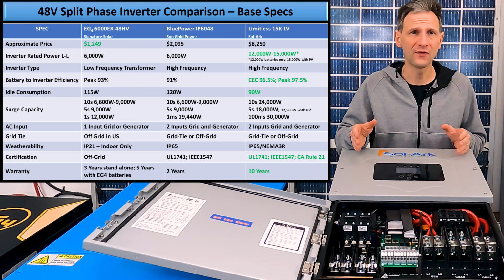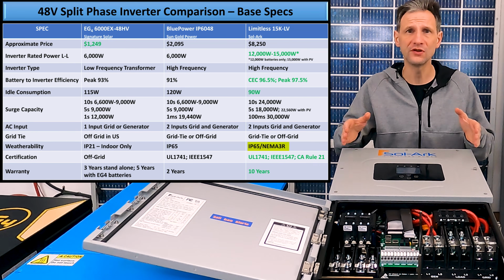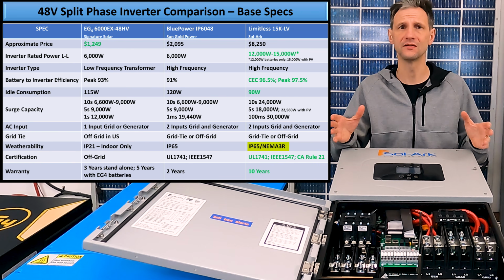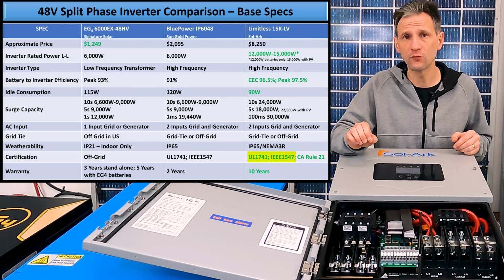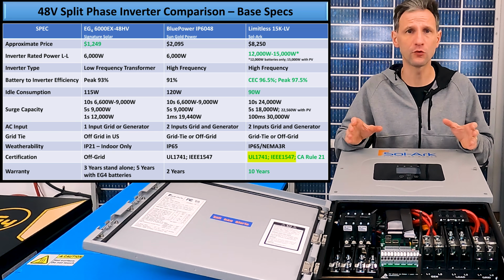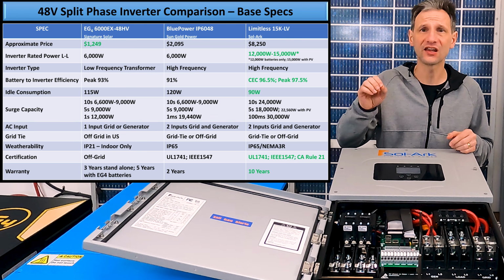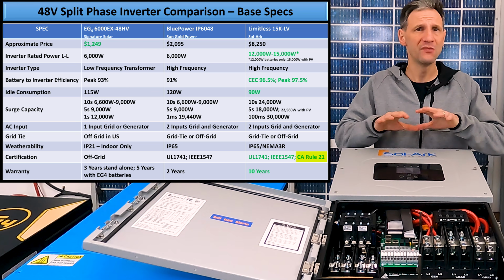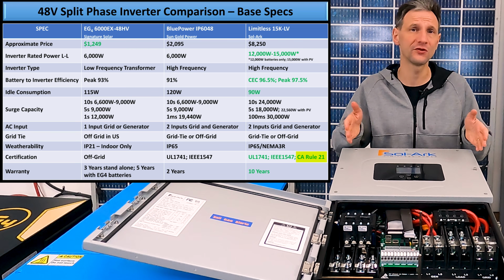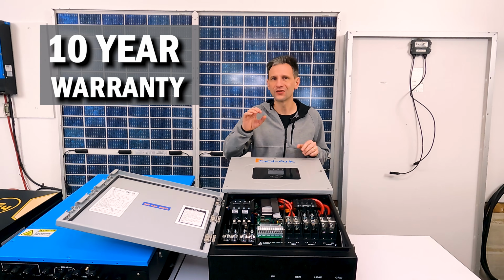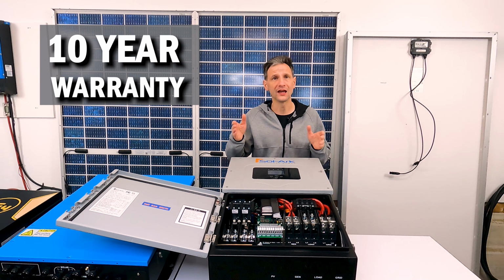With IP65 and NEMA 3R rating, this unit can be mounted outside if needed. It meets UL 1741 and IEEE 1547 standards, and the California Rule 21, making it the only one of these three to be certified in California. It also has the best warranty of all three at 10 years.